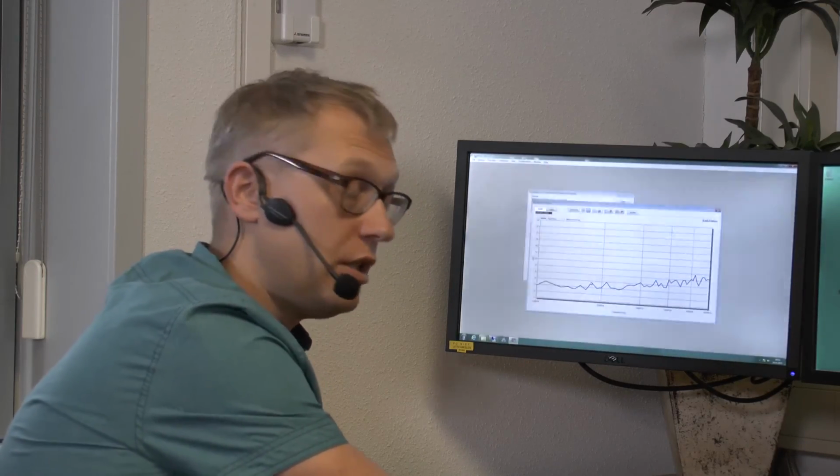Okay, so looking at the overall error graph, I see that the RadiField is well within the 0 to 6 dB limits, which is required in the standard. Yeah, that's correct. The RadiField is below the 6 dB limit. Okay, John, thank you for this clear demonstration.